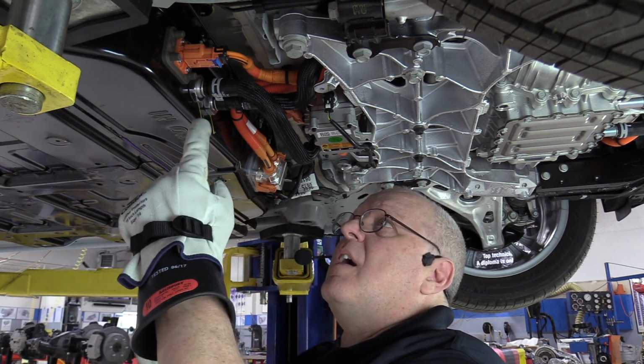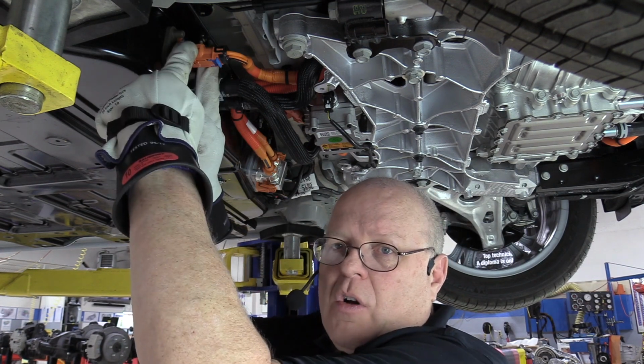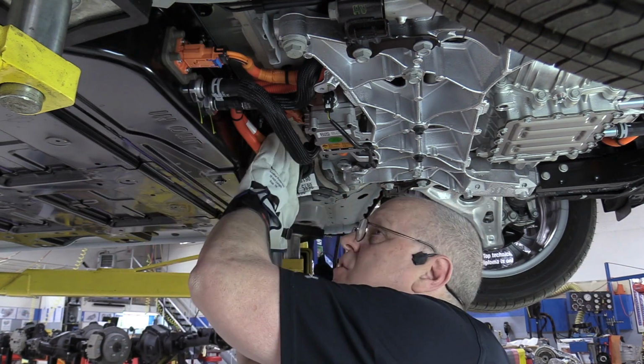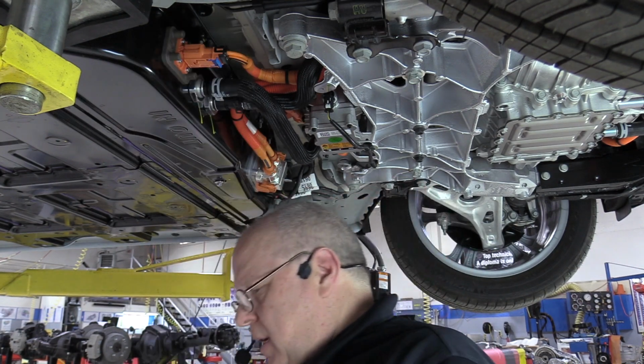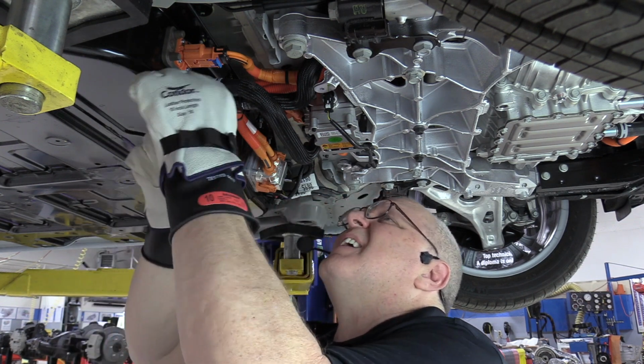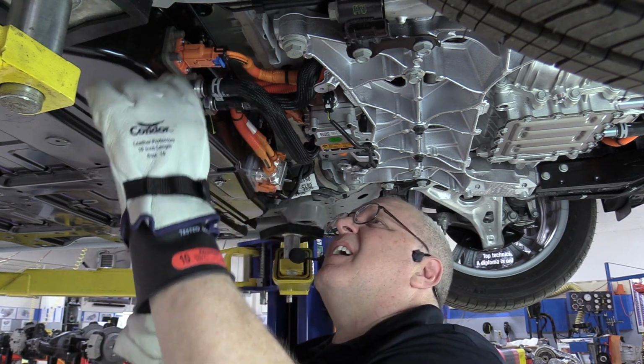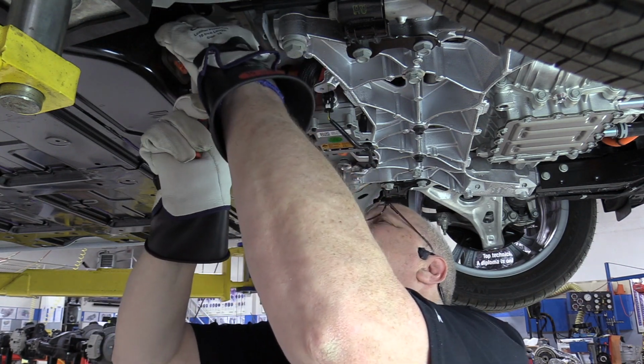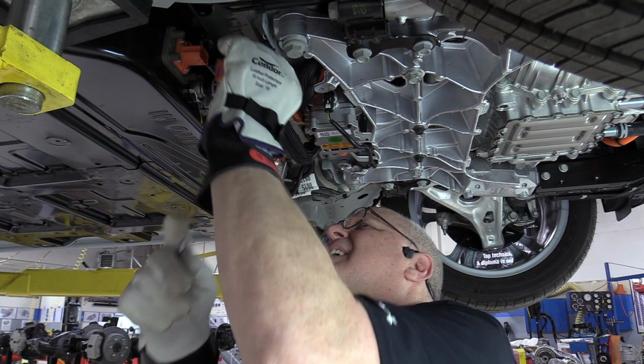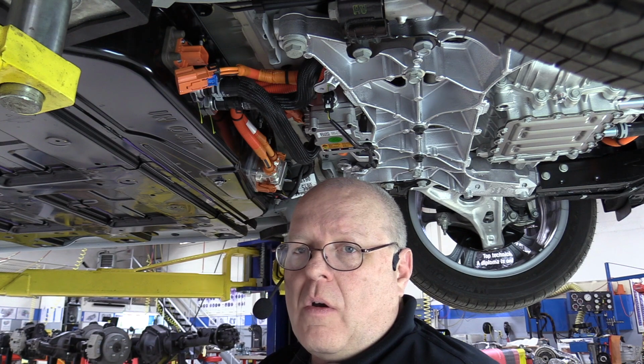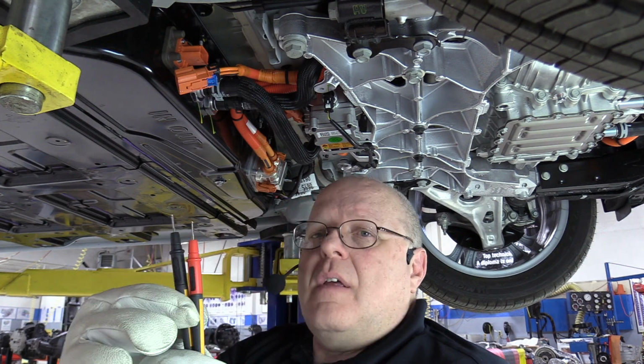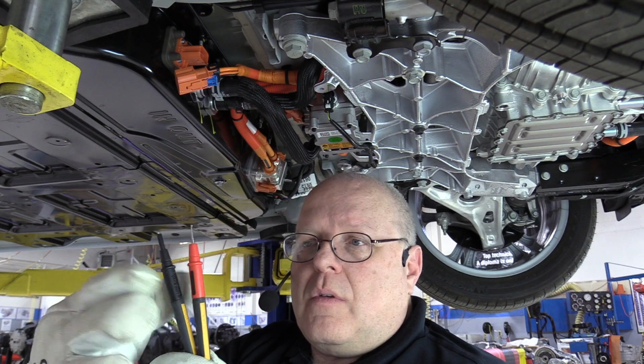So the disconnect procedure continues with checking to make sure we do not have high voltage on both the large electrical connector and the small electrical connector. So the procedure is to release the connector position assurance clip and unplug the charger connector. And then using the same multimeter, a category 3 meter with category 3 leads. Right here they're category 4. I have to turn the twist lock there to get them to be category 3.